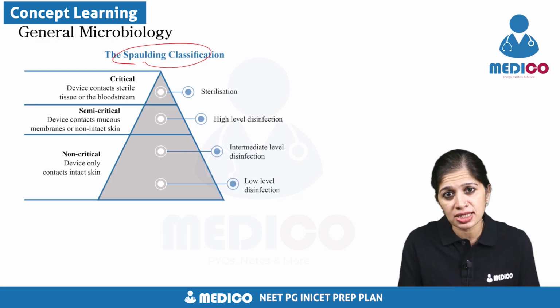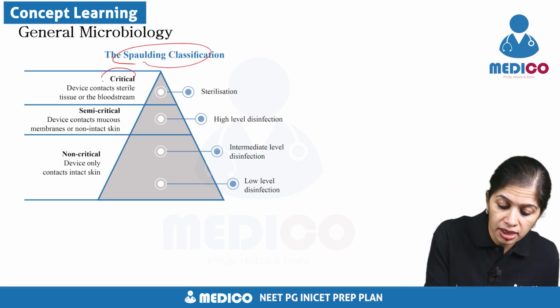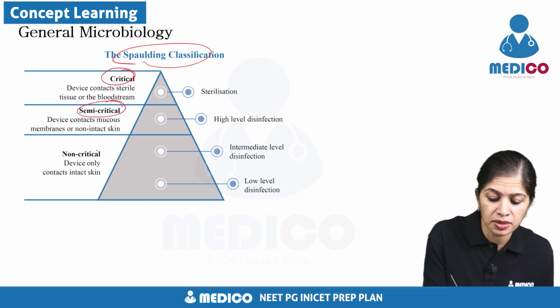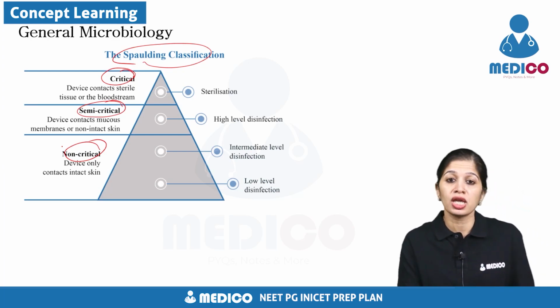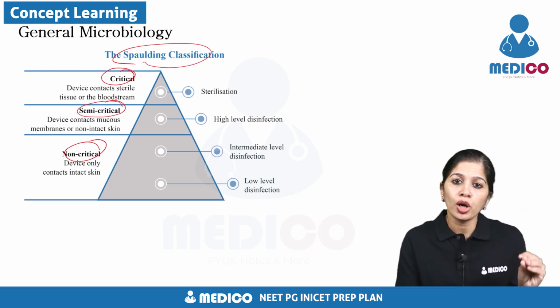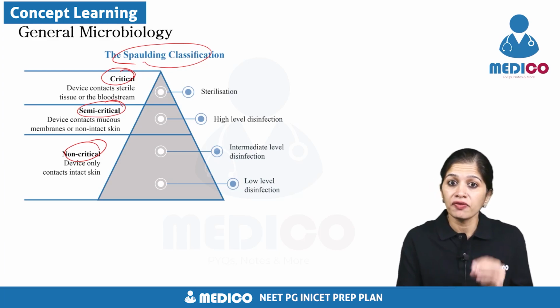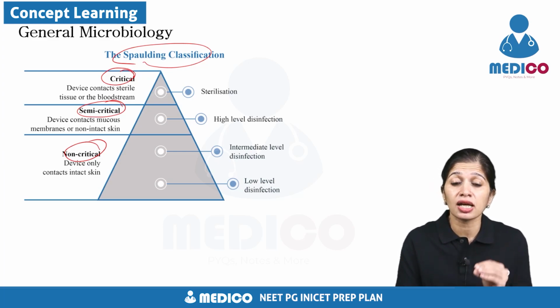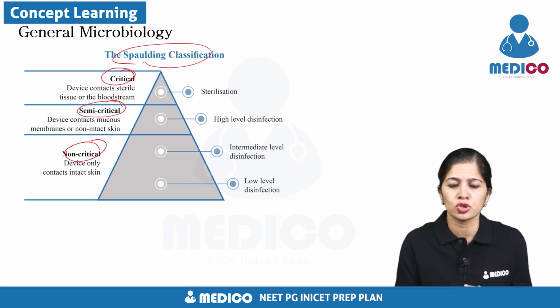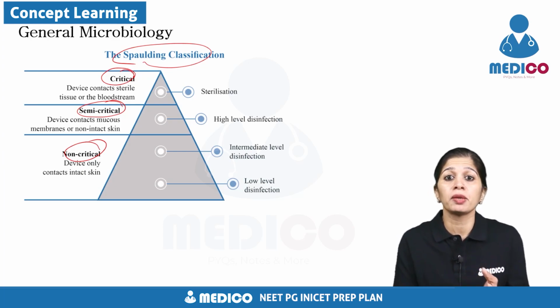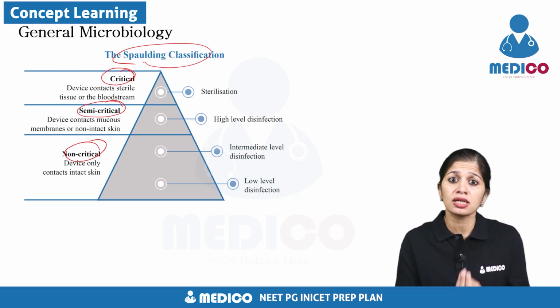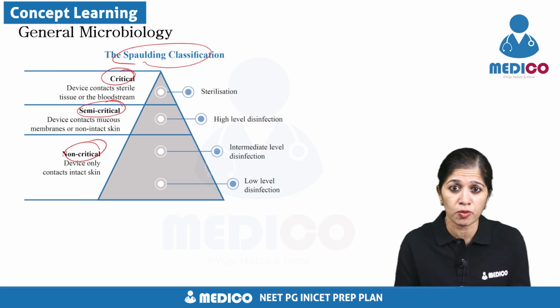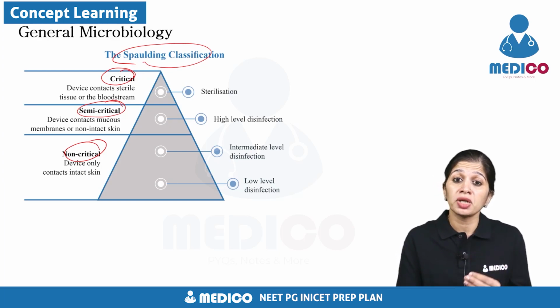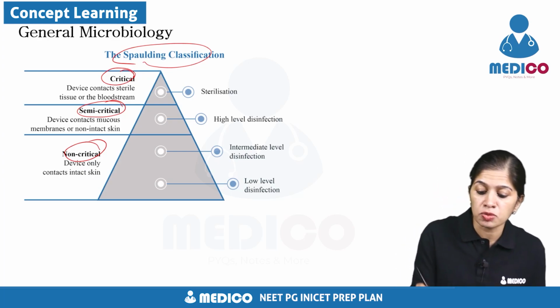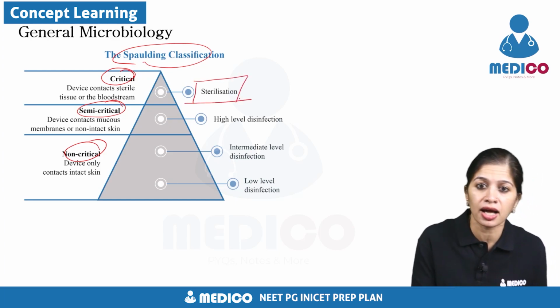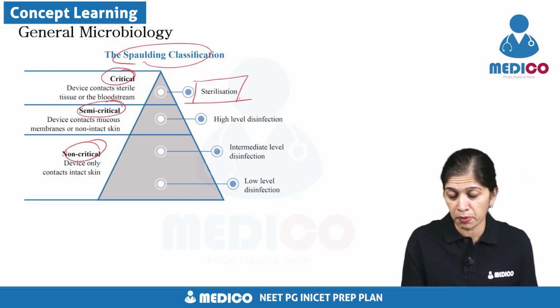So, Spalding has classified items into critical items, semi-critical items and non-critical items. So, the name itself explains it. What is a critical item? A device that comes in contact with a sterile body tissue or bloodstream. So, imagine something like, say, a surgical instrument. It is coming in contact with a bloodstream or with a sterile body tissue. So, that means it is a critical item. Critical items should always be sterilized. Remember this point.